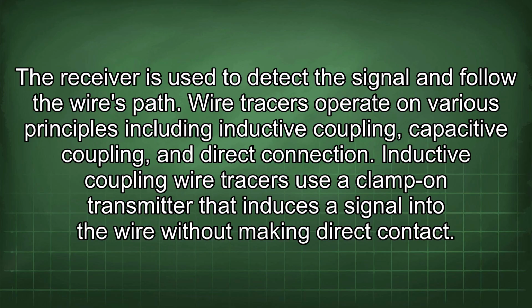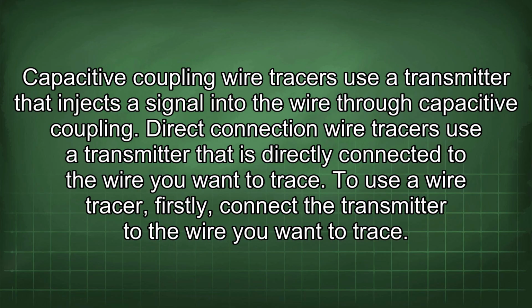Wire tracers operate on various principles including inductive coupling, capacitive coupling, and direct connection. Inductive coupling wire tracers use a clamp-on transmitter that induces a signal into the wire without making direct contact. Capacitive coupling wire tracers use a transmitter that injects a signal into the wire through capacitive coupling. Direct connection wire tracers use a transmitter that is directly connected to the wire you want to trace.